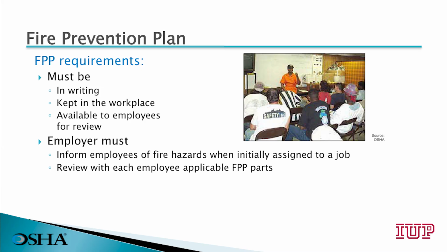Fire prevention plans must be in writing, they need to be kept available in the workplace, and available to any employee for their review. An employer must ensure that the employees are aware of all potential fire hazards when they're initially assigned to a job. And the employer must review with each of those affected employees all components of the fire prevention plan.